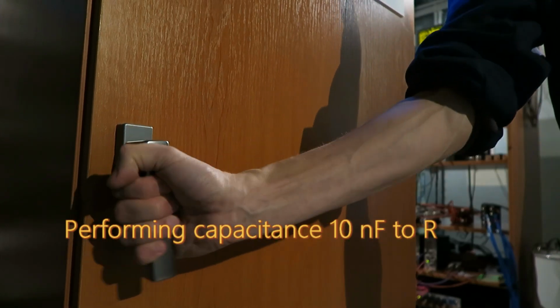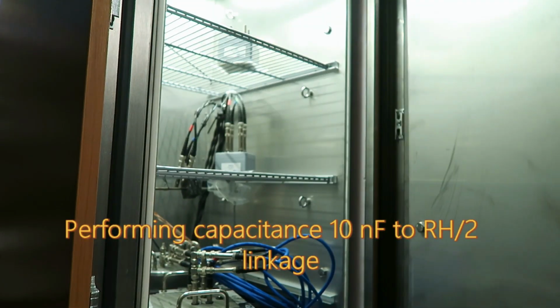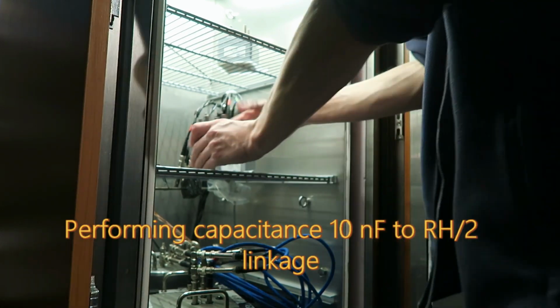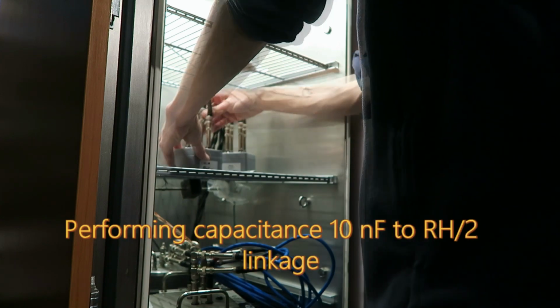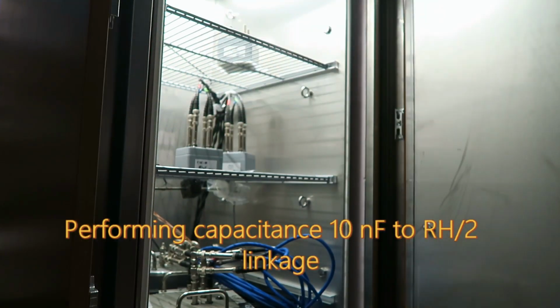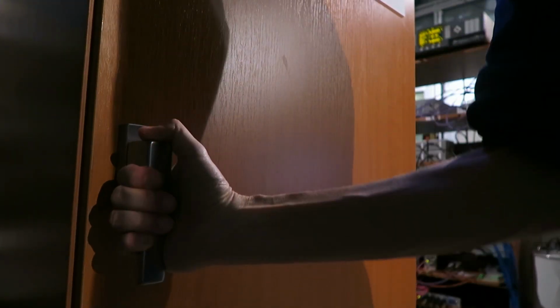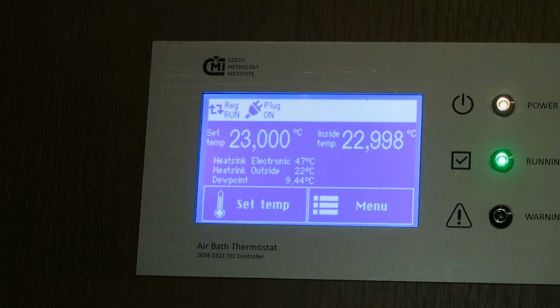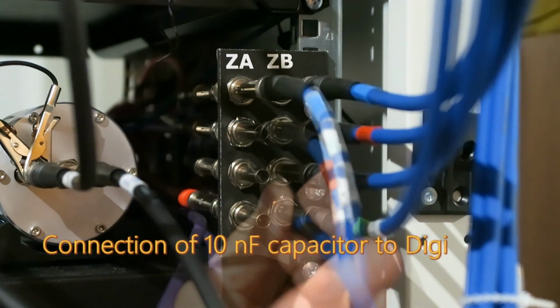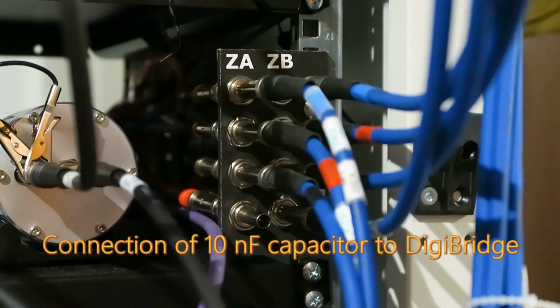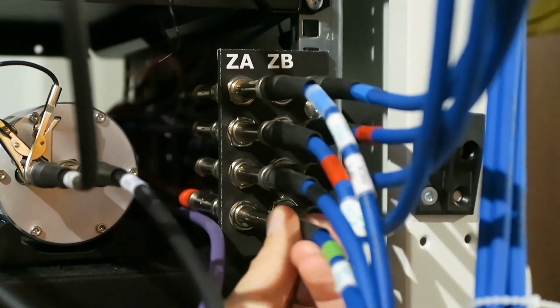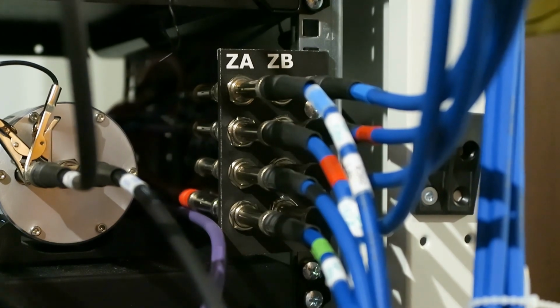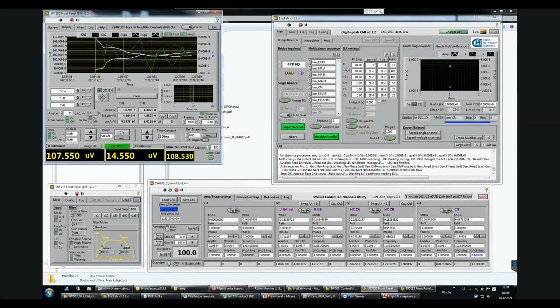We will perform direct comparison of a capacitor against AC QHR at frequency of 1233 Hz. We will use a 10 nanofarad capacitance standard. Let's stabilize it in an air bath and simply connect it to the bridge. A 1-to-1 impedance ratio measurement is performed in the fully digital mode.